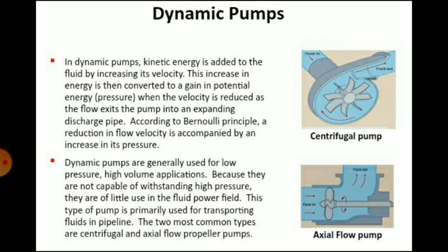Dynamic pumps are generally used for low pressure, high volume applications because they are not capable of withstanding high pressure. They are of little use in the fluid power field. This type of pump is primarily used for transporting fluids in pipelines. The two most common types are centrifugal and axial flow propeller pumps.